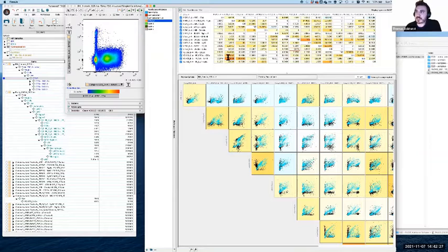The number, as we discussed, is simply a ratio from the primary detector to the secondary detector for that particular fluorophore. In most panels, you shouldn't be expecting to see compensation values of 100 or above. It depends on the exact fluorophores you're using, how much overlap they have, and the individual detector settings. But for reasons we don't have the time to get into, you can have compensation values of 100 or above, and that can be totally okay.